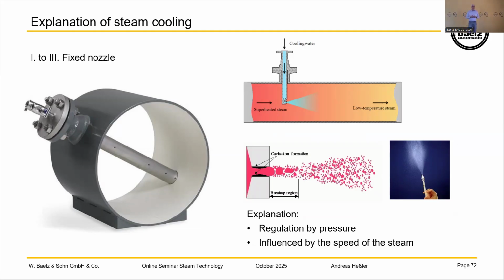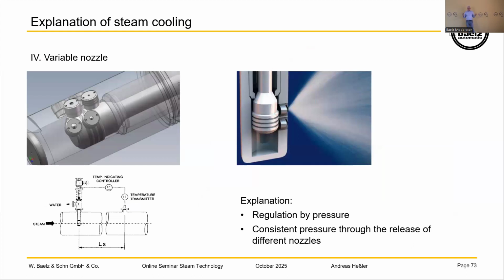First, we have the fixed nozzles. The fixed nozzles are regulated by pressure. Lower pressure means lower mass flow, which also means bigger water droplets. Higher pressure means more water flow and smaller droplets to cool down the steam. The next one would be the variable nozzle. I already told you it also works over pressure, but in this case we have different kinds of nozzles with different kinds of KVS, so we can open and close. So the nozzles always work with the highest pressure drop and with the best spraying picture.